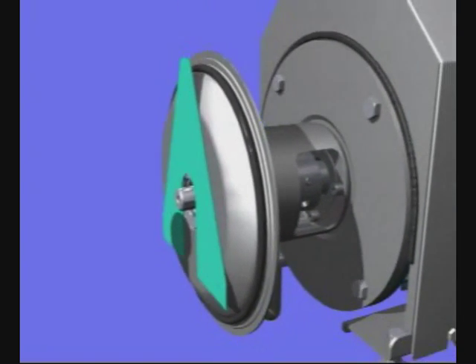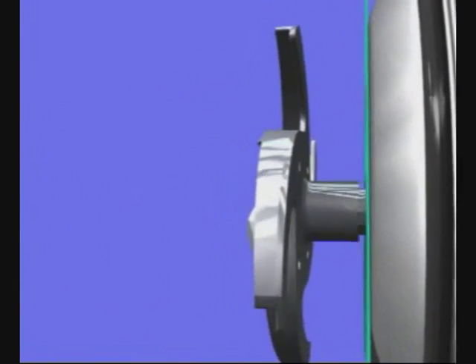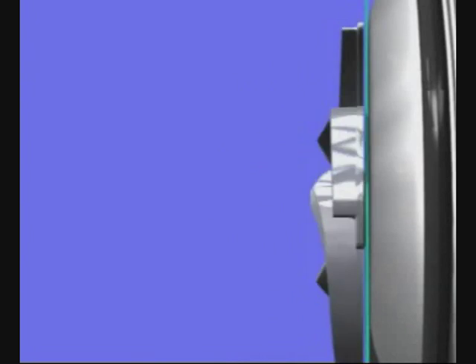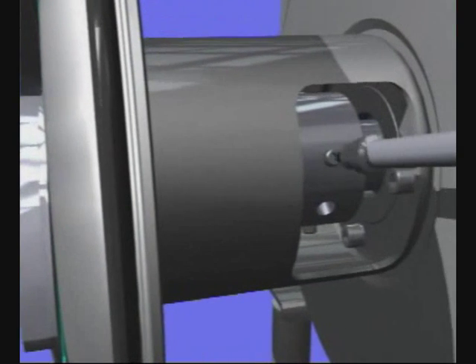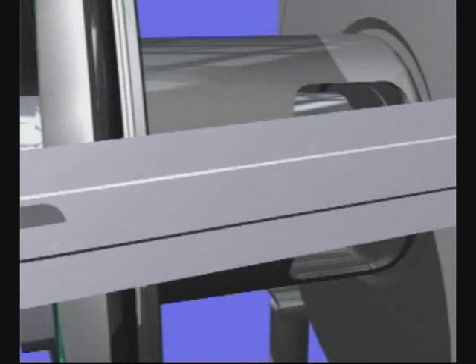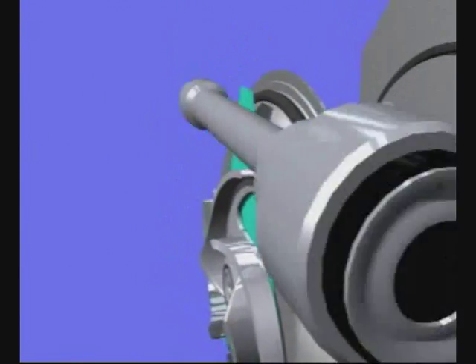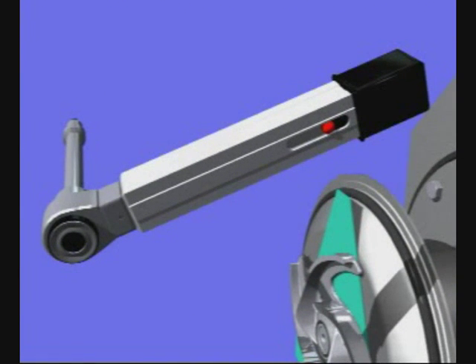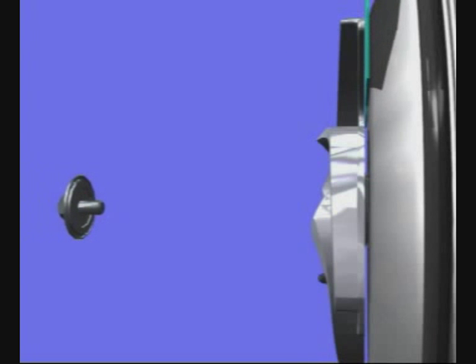Insert the 1mm impeller setting tool before fixing the impeller and impeller screw. When the impeller is tightened, you must tighten the pin screws in the coupling to a torque of 18 Newton meters. Now remove the distance piece and assemble the rest of the pump as demonstrated previously.